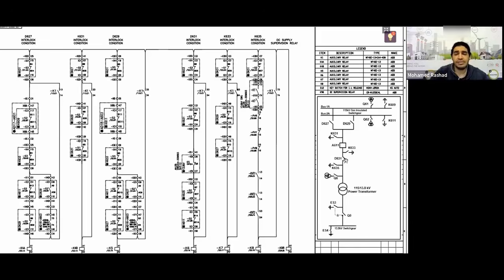Now, with the 6113, it's not just that the air switch is open. The air switch is open, and also, what position should it be in? It must be in the position where the door or the section of the air switch is closed. In this case, when it comes down, I want to close the ground, so I bring the knob switch and put it in the position to open the section door. When I press the push button, I will find that the interlocking magnet does not engage or work with me.